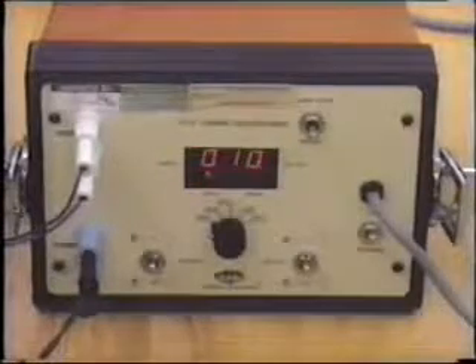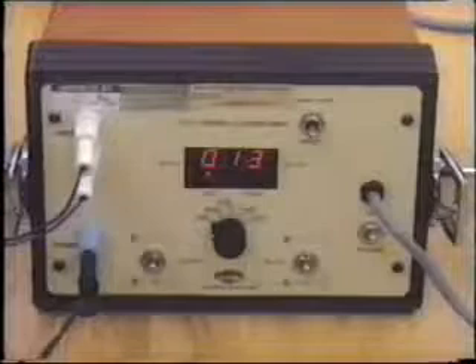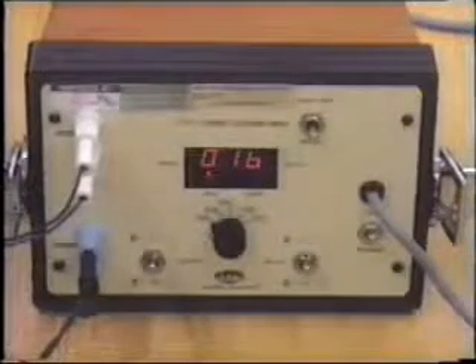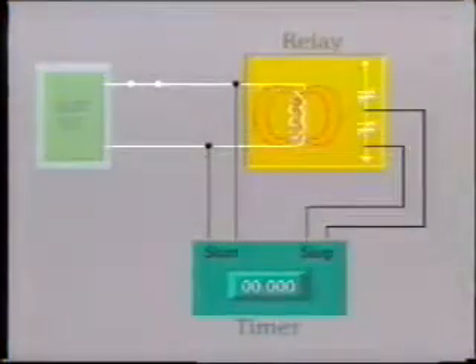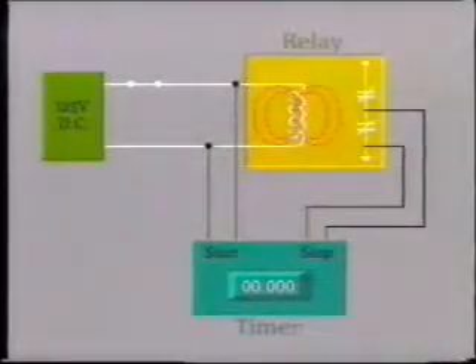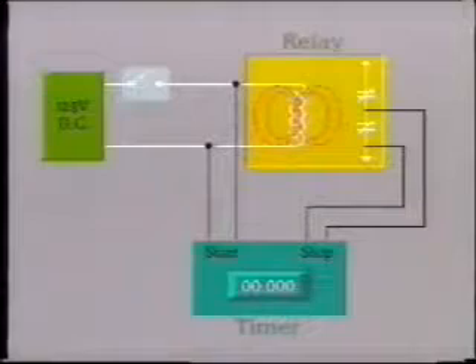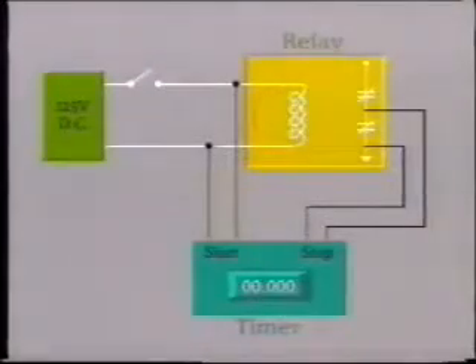For example, here we have a Doble FT2 timer, which is set up to measure the dropout time of a relay. The timer will start when the relay coil is de-energized and will stop when the relay contacts open. But look, this relay operates on 125 volts DC. As we have mentioned before, when the DC current is interrupted, the magnetic field set up by the current collapses. This in turn may induce a voltage in the stop circuit, which can cause current to flow in a direction such that a premature stop signal will be produced. In fact, the timer will probably read 0.